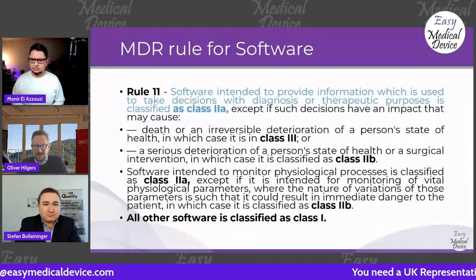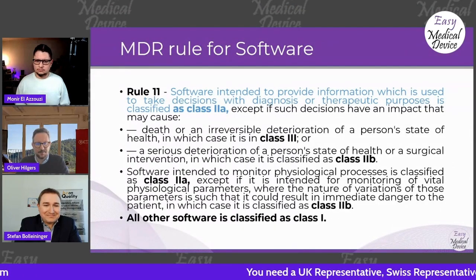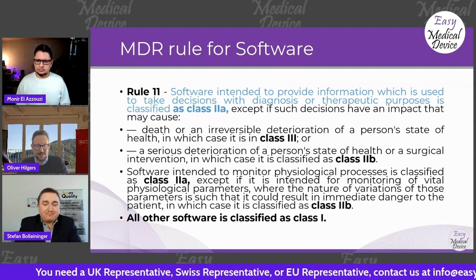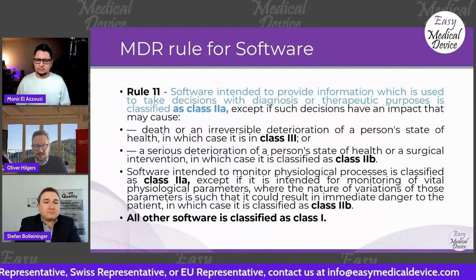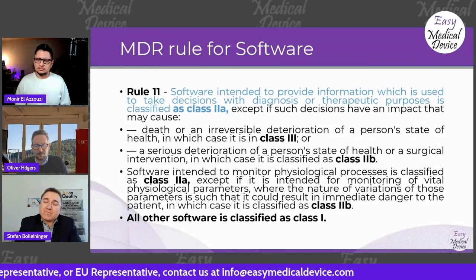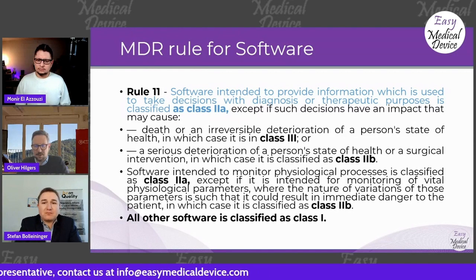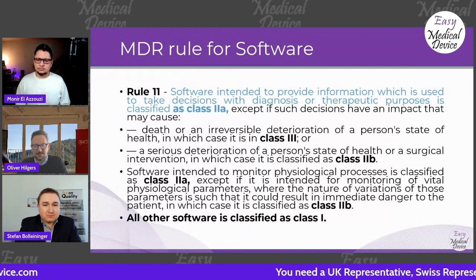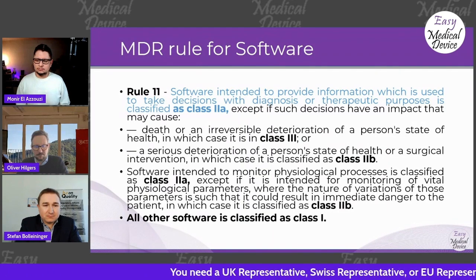So a lot of software, if you just purely look at Rule 11, if you literally read it, then more or less everything needs a notified body. And as often, maybe under MDD, we had kind of, let's say, an under-regulation for software. And I think if you look at Rule 11, it's kind of the opposite. It sounds like rather an over-regulation, and I think both are not correct. So the middle should be found, and I think that's one of the goals for today, to contribute to get more clarity. That there is not black and white here. There's something in between as well.